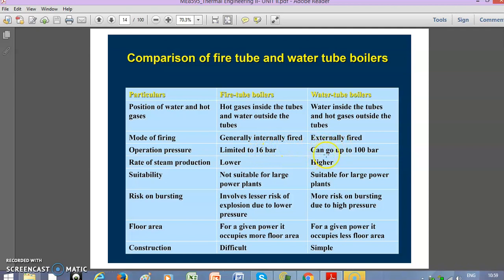Large power plants or high capacity plants use water tube boilers, which can operate up to 100 bar. The rate of steam production is lower for fire tube boilers, while water tube boilers have a larger steam production rate in kg per hour. Fire tube boilers are not suitable for large power plants, so for large power plants we definitely use water tube type boilers.